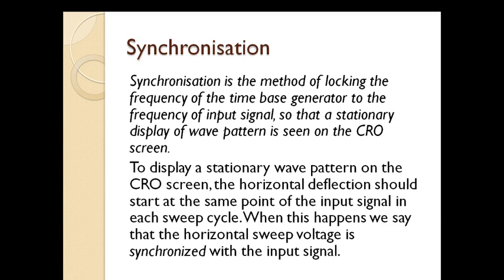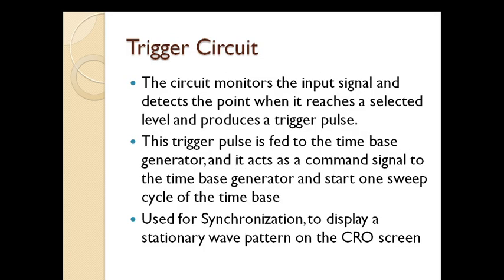The moment the vertical plates start receiving the input signal, the sawtooth wave must simultaneously be provided to the horizontal plates, so that the signal going to the Y-plates and the sawtooth wave going to the X-plates match in every sweep cycle. This creates a steady, stationary wave pattern on the screen of CRO. Synchronization is thus a method of locking the time-based generator's frequency to the input signal's frequency going to the vertical deflecting plates.